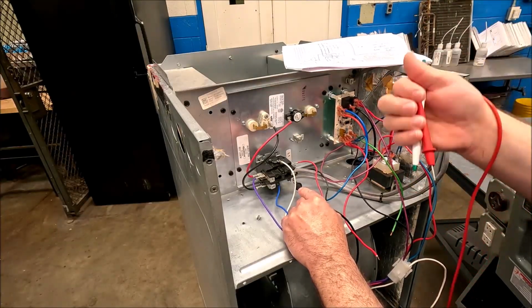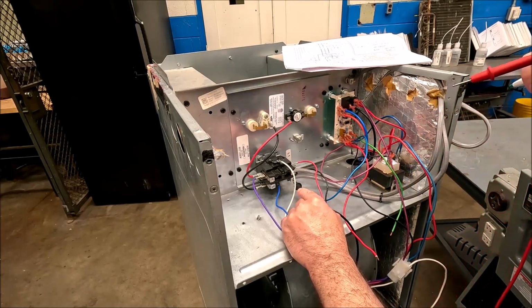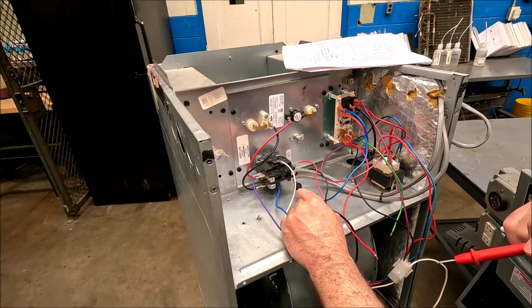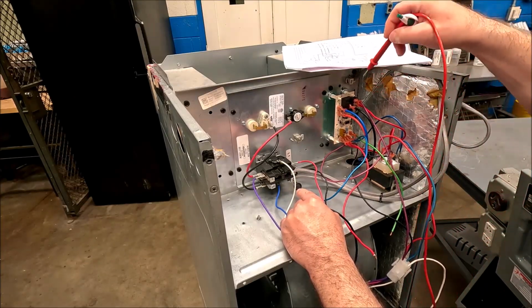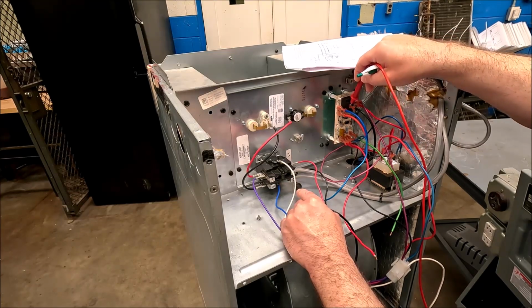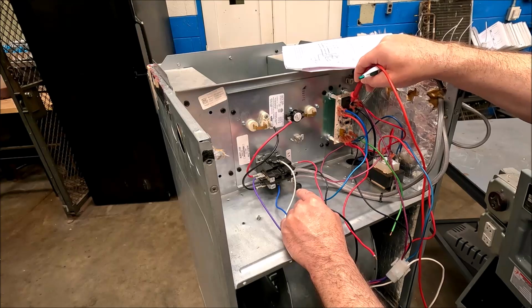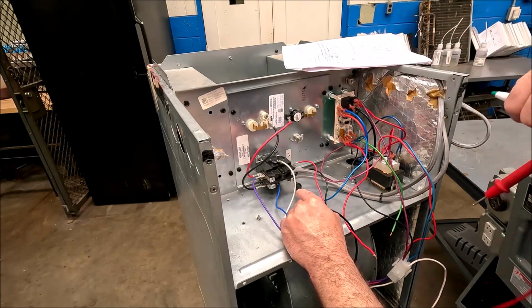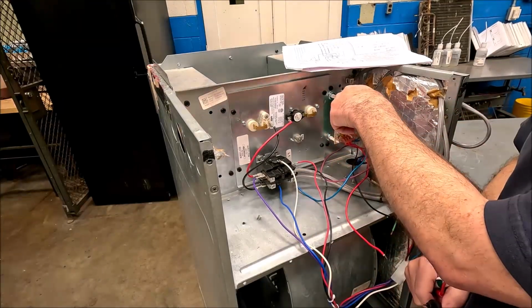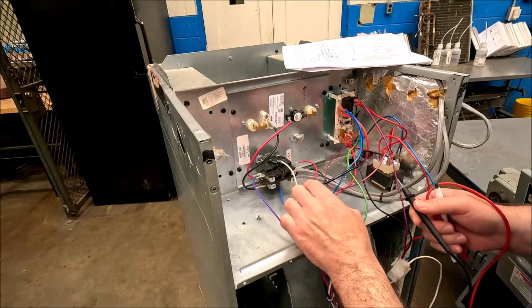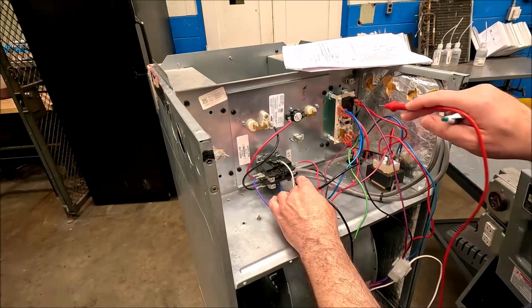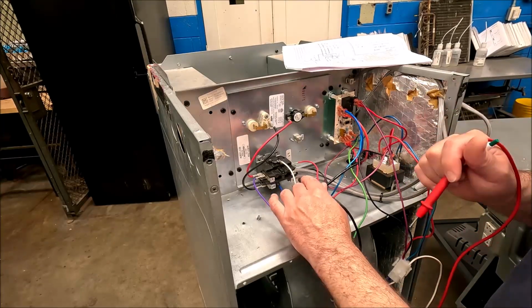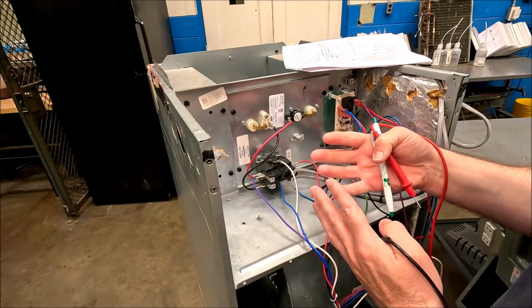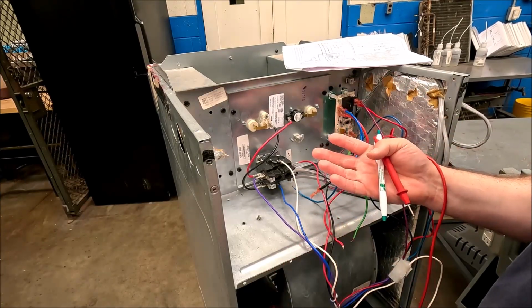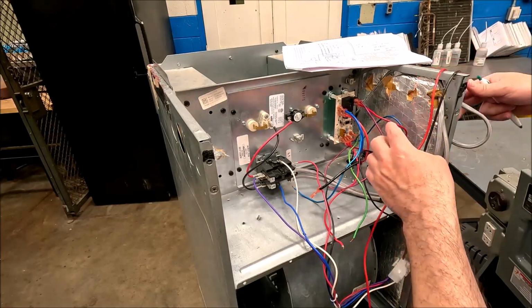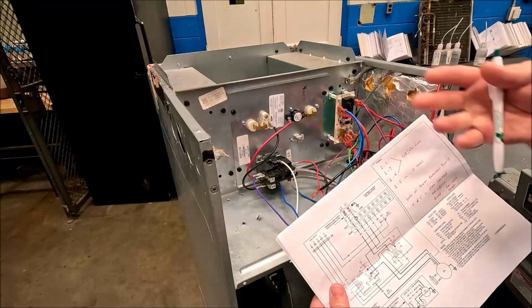But my point to the voltage part of this is you are essentially giving yourself the hopscotch on the circuit that you're looking for. And when I find power going into the relay but not coming out of the relay, my number 5 is right here on this common terminal. If everything said 240 and then I get here and it's 0 because it's not coming out, I would move this wire. Don't check the wire leaving the relay. I would pull that wire off and check that relay. But when you have 240, 240, 240, and all of a sudden you have 0, there's your problem, right? You've just found it. So hopefully you can follow that example. Hit me up with a comment if you need to, but that's how I would use it on the voltage.